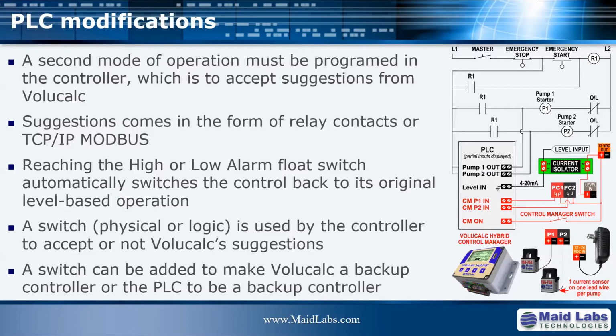And a fringe benefit of this is that in lift stations, most of the control equipment has backup. I mean, you have 2 pumps, you have spare floats, you have a bunch of things that are related to backups, but you don't have a backup PLC. It would be possible to just put in a switch to transfer the control to the Volucalc if you would need to repair the PLC, and then after that, get it back.